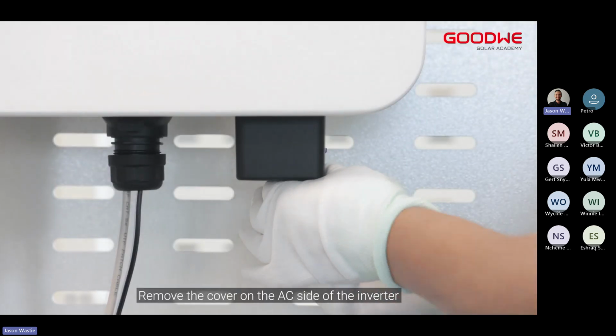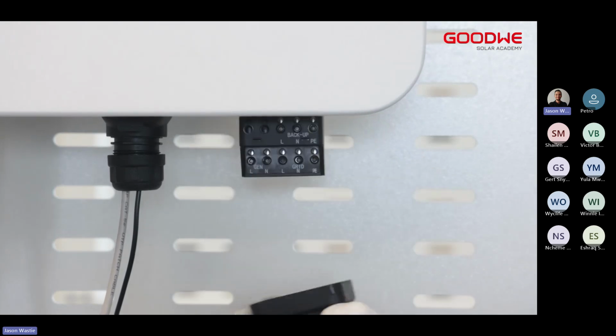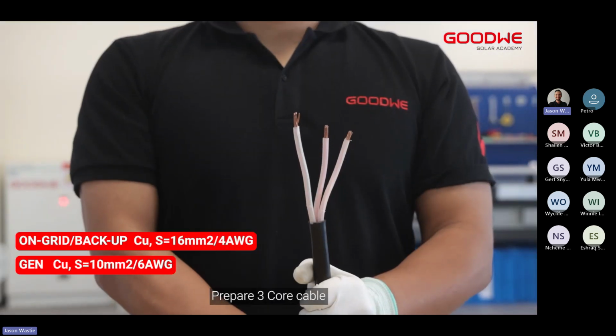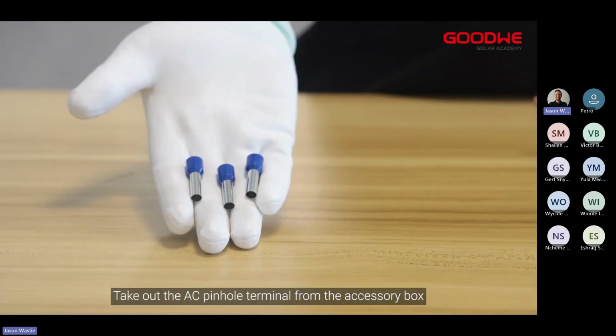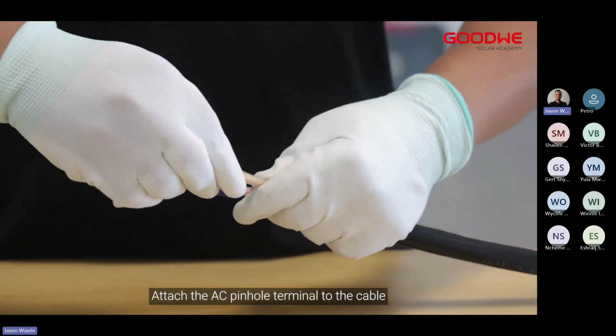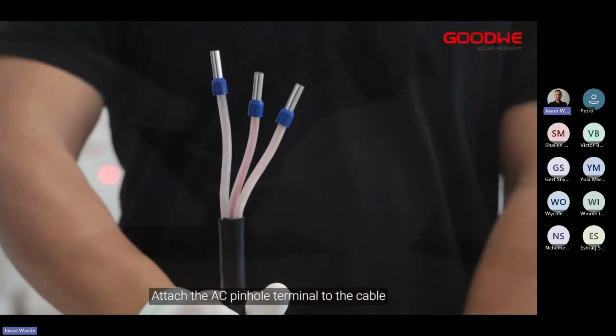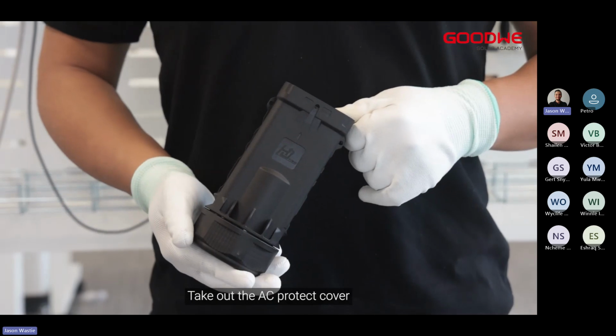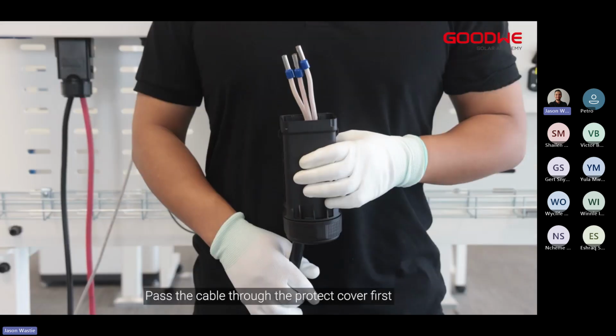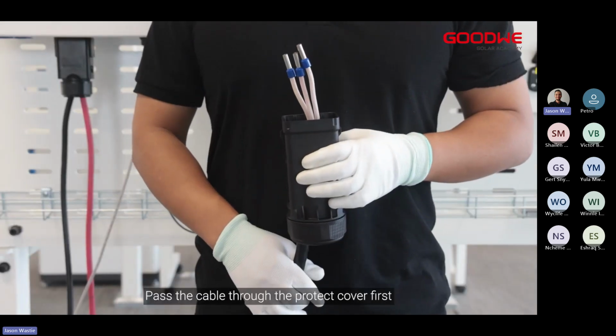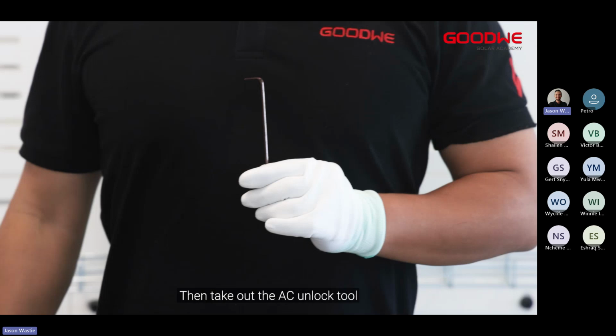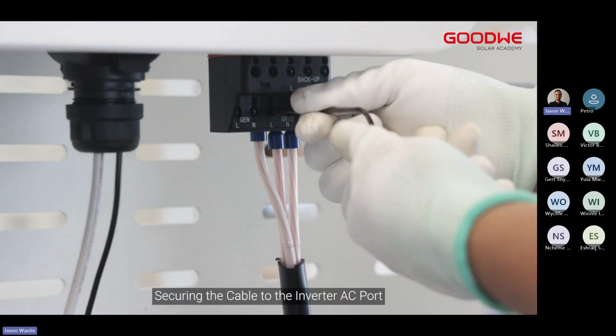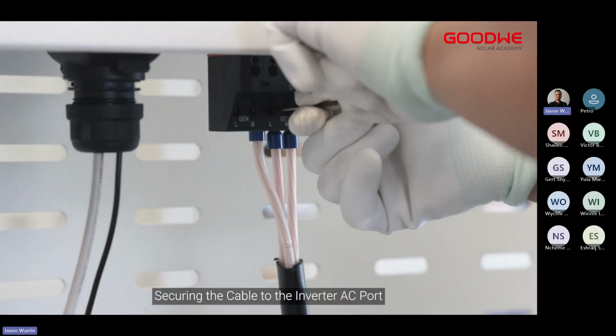Remove the cover on the AC side of the inverter. Prepare 3-core cable. Take out the AC pinhole terminal from the accessory box. Attach the AC pinhole terminal to the cable. Take out the AC protect cover. Pass the cable through the protect cover first. Then take out the AC unlock tool. Securing the cable to the inverter AC port.